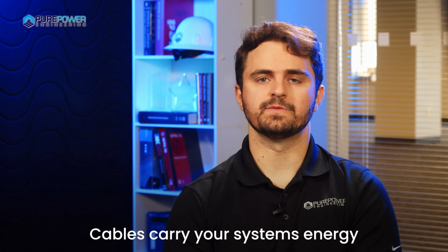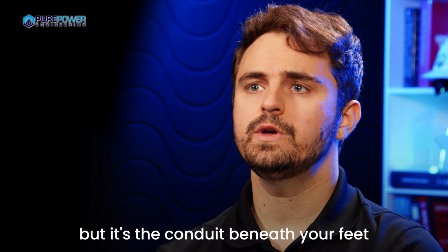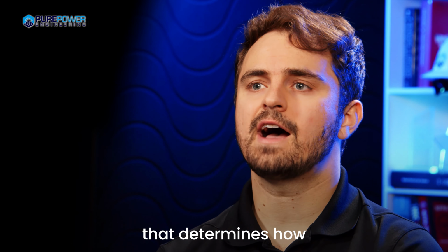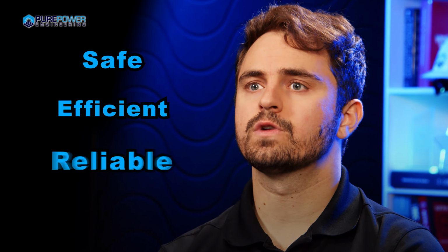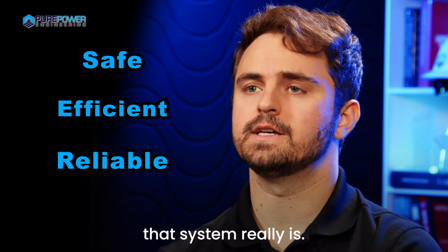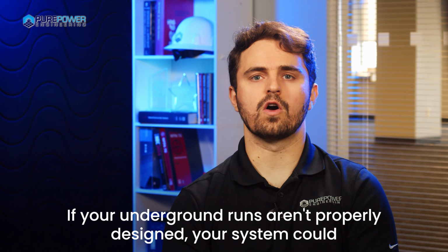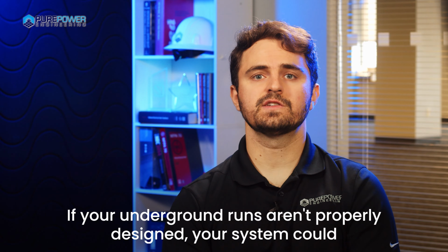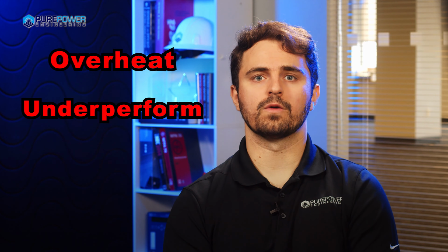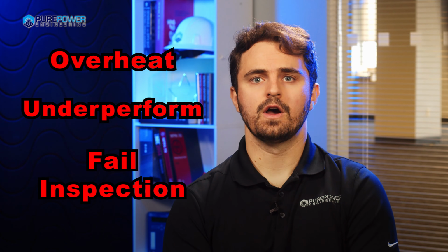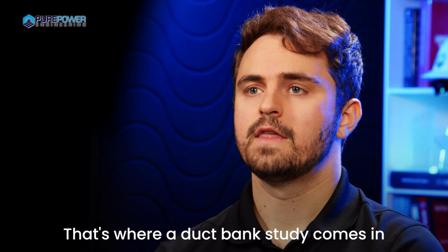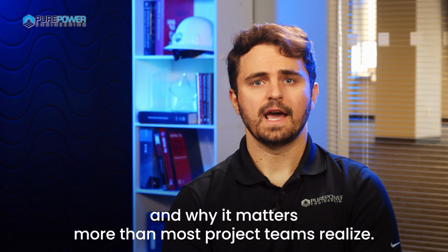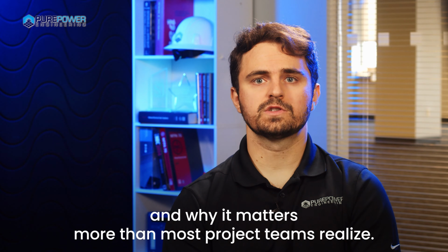Cables carry your system's energy, but it's the conduit beneath your feet that determines how safe, efficient, and reliable that system really is. If your underground runs aren't properly designed, your system could overheat, underperform, or fail inspection before it even gets turned on.